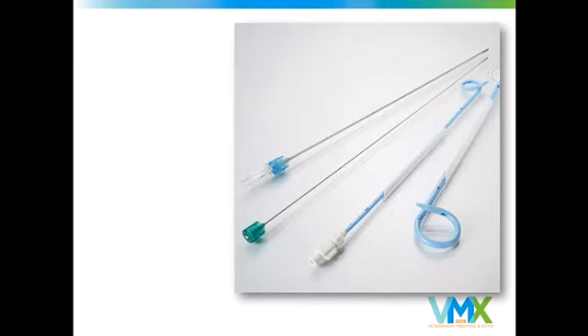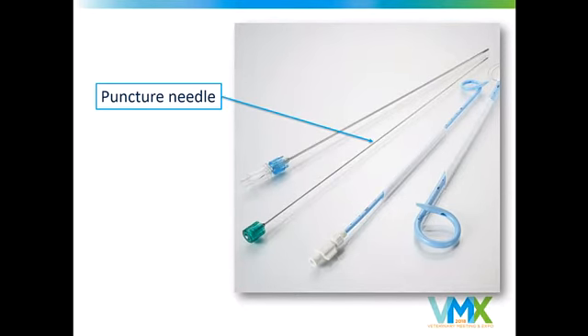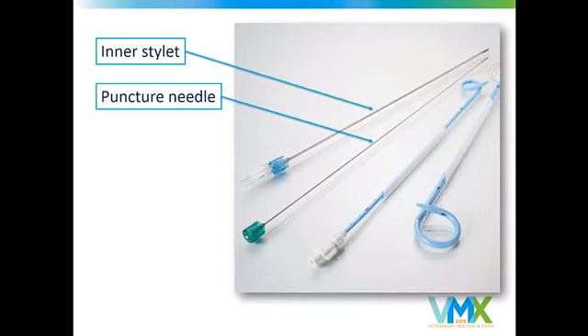So they all have basically the same standard components. The very, very central part is a sharp puncture needle. It's got a cutting end on the tip. It's extremely thin. This sits inside the hollow trocar, or the inner stylet. And then these two things together sit inside the catheter. Depending on the size of the catheter, they have a very strong determination to make their pigtail. As soon as you get them out, they are going to pigtail themselves.